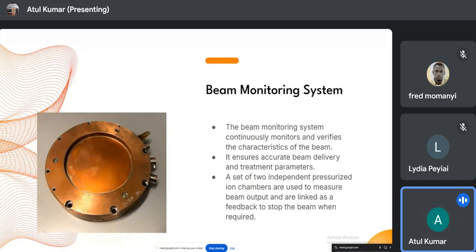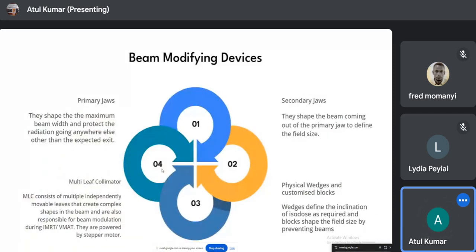Beam modifying devices: there are primary jaws. I hope all of you medical physicists know about the jaws. The jaws are like bricks in shape. They are motorized, and they come in regular sizes. The primary jaw is just the slit. As I told you, when the X-rays are being generated, they are covered from all around with either depleted uranium or a very high atomic number material like lead, or high density tungsten, to block X-rays going in any direction except a small slit. That slit is called the primary jaws. That is the primary collimator.